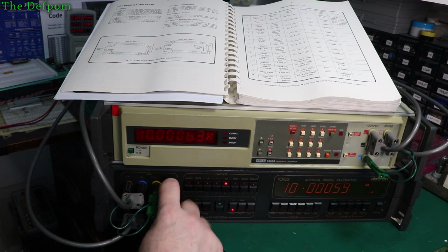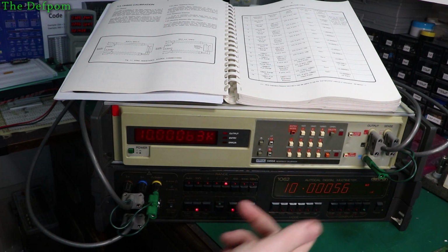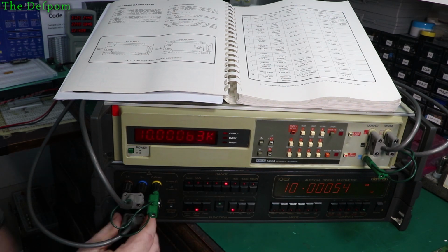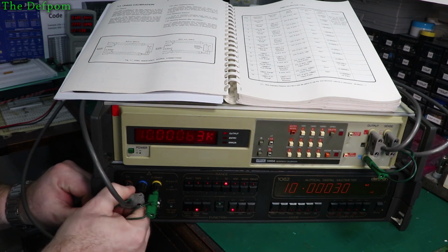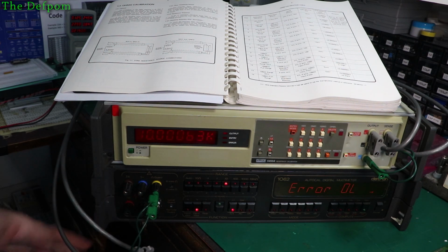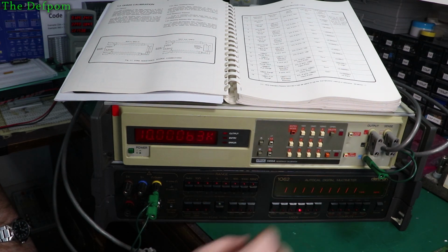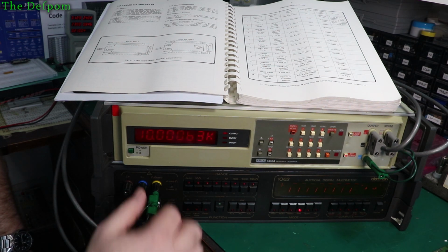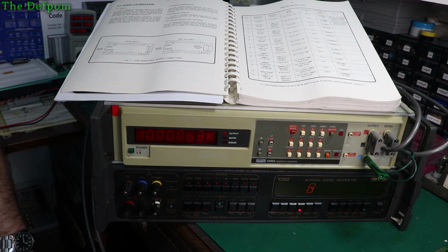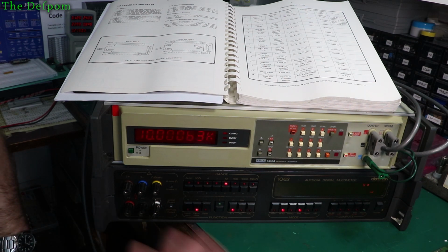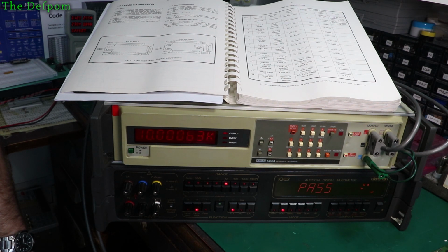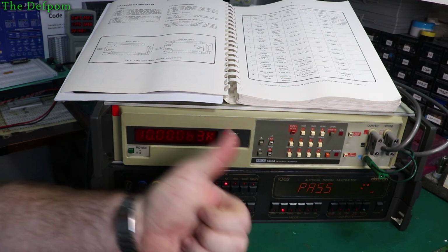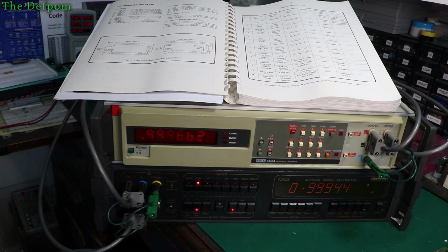So that's on 4-wire. Put it back on 2-wire. It doesn't make a difference because I've got all this stuff hooked up anyway, so it links them together and it doesn't actually matter. Let's do the self-test again on 2-wire. Let's unplug that in case it matters. It shouldn't, but. Passed. Right, excellent. So yes, I can calibrate at 19. Excellent. I'm going to do this again.